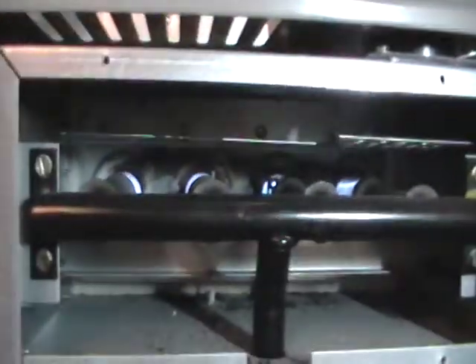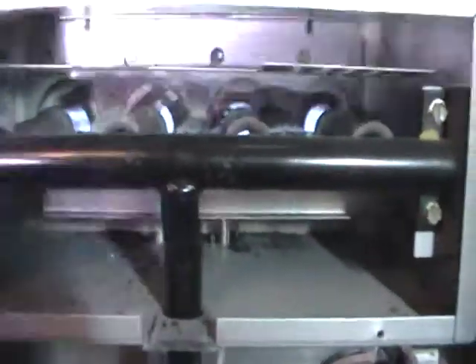Now here you can see that the heat exchanger is a little bit corroded around where the burners are. That's a little bit of a concern, but as long as there's not too much scale there and that the heat exchanger is still intact, you can always have a professional come in and take a look at the heat exchanger to make sure that everything is in good working order and that a little bit of corrosion isn't a sign of a bigger problem.